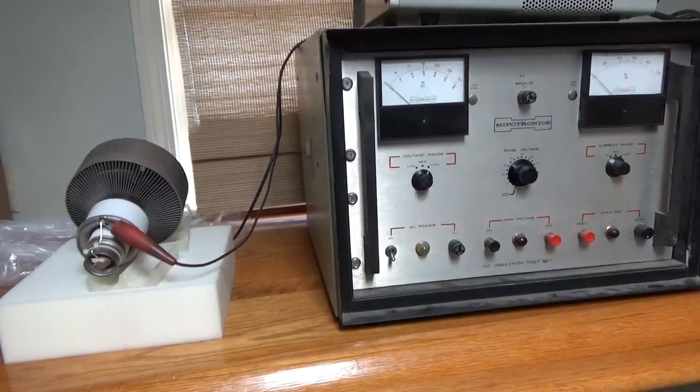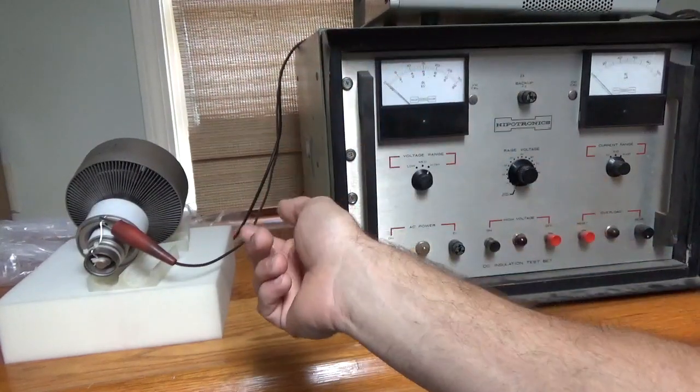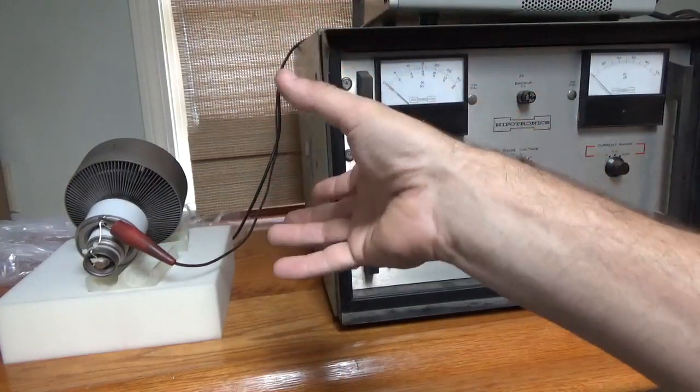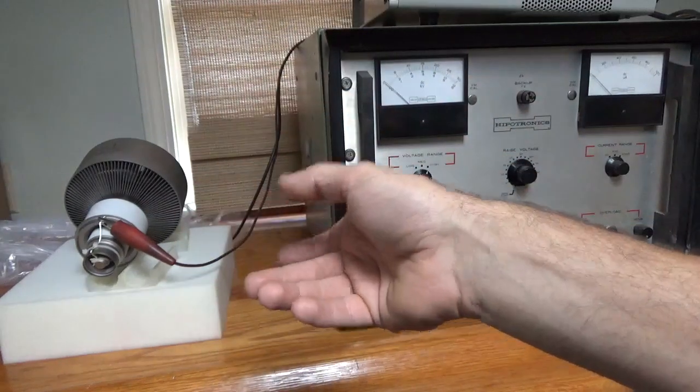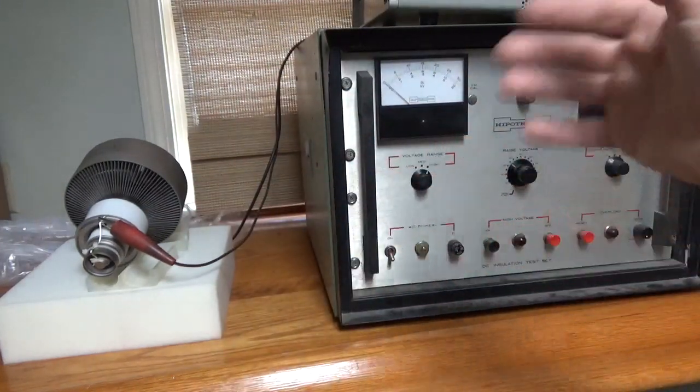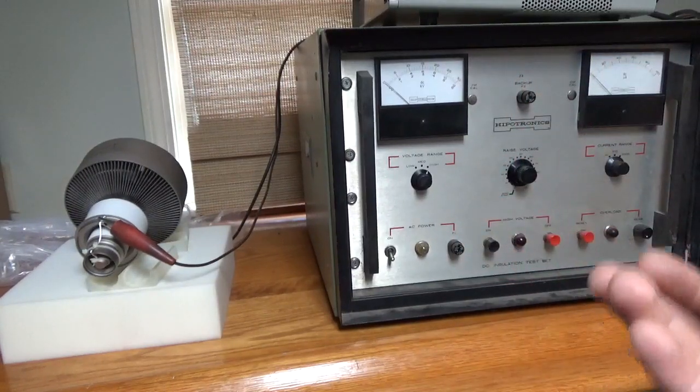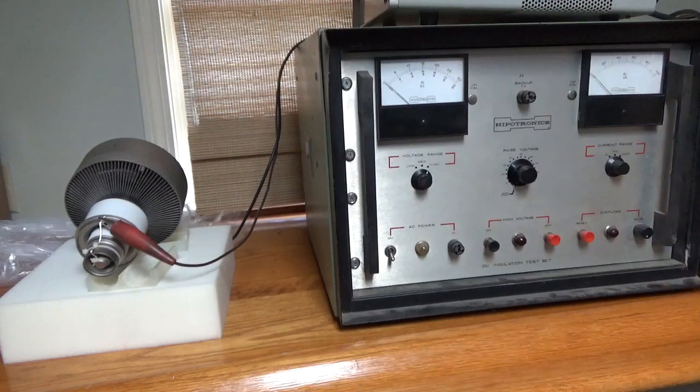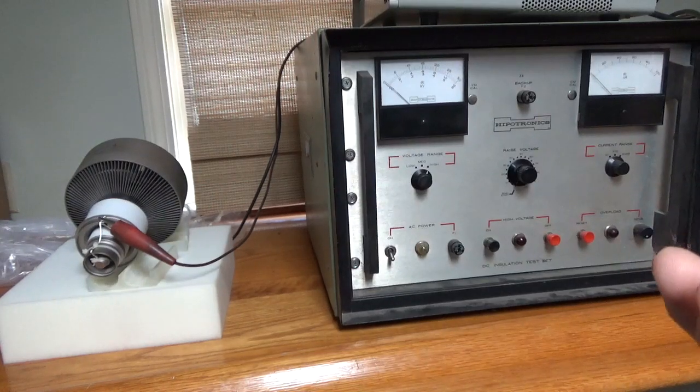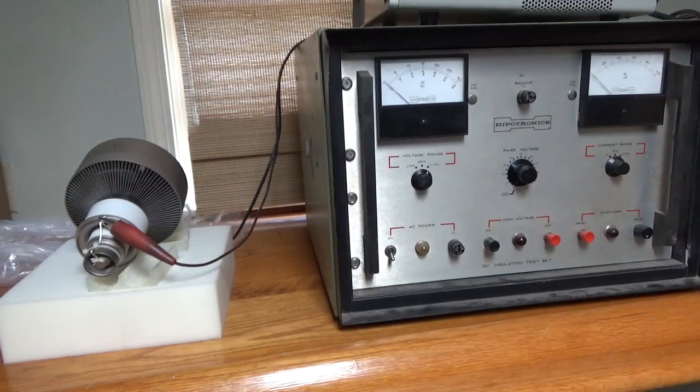Okay, I'm going to go ahead and retest it. It's up on plastic. I cleaned the ceramic portion. The Chinese tubes have a glazed ceramic. You always want to make sure that's nice and clean. I just wiped it down. It's a brand new tube. I didn't touch it, but someone before me probably touched it.